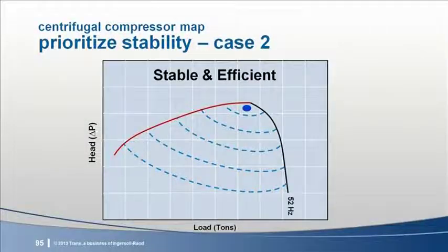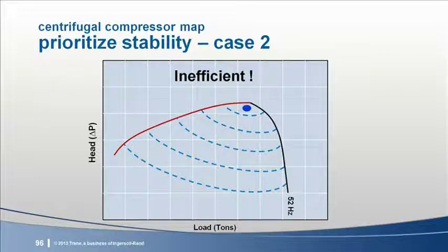Let's look at the impact of the opposite form of instability, rapidly decreasing condenser system temperature. Just for the sake of the example, let's say the system conditions are requiring the compressor to operate at this point. Now, what happens when a cooling tower fan is turned on or quickly ramped up in speed? The condenser water temperature drops, causing the required compressor lift to drop as well. This would not cause surge, but the compressor capacity rises slightly, causing the leaving chilled water temperature to drop below set point at a lower compressor efficiency.